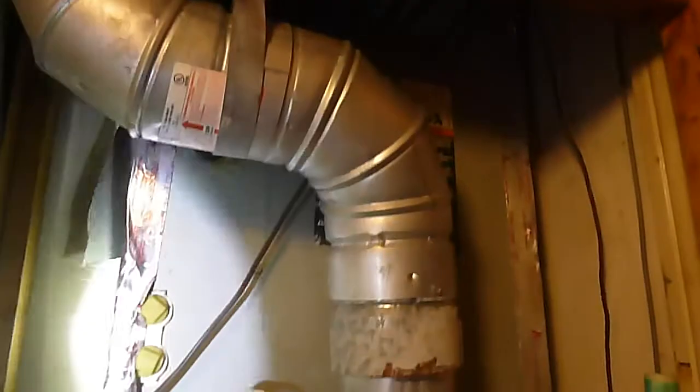It's closer than 10 feet. This is the upstairs indoor air handler. The upstairs indoor air handler, it gets its air. It's the only air I can find. What it drags out from underneath the door there, and then that would be the makeup air there. But it's getting all of its combustible air, all its air requirements, ventilation requirements from the interior.